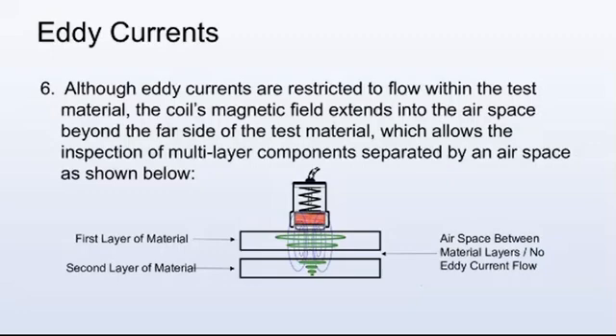Although eddy currents are restricted to flow within the test material, the coil's magnetic field extends into the airspace beyond the far side of the test material, which allows the inspection of multi-layer components separated by an airspace as shown below.